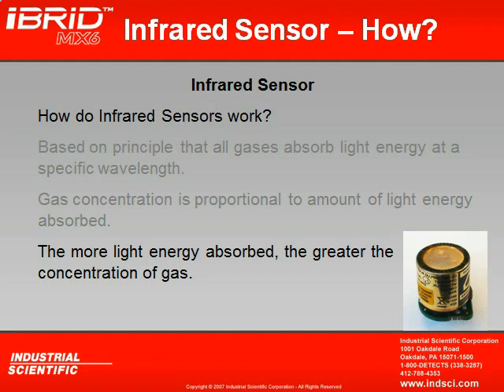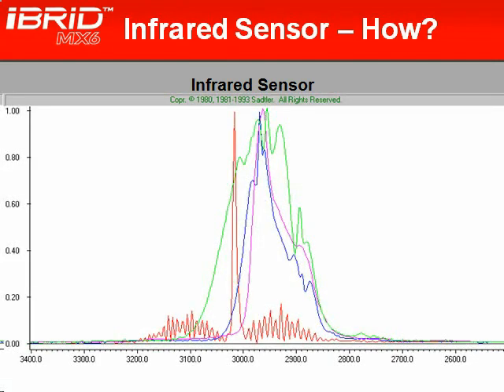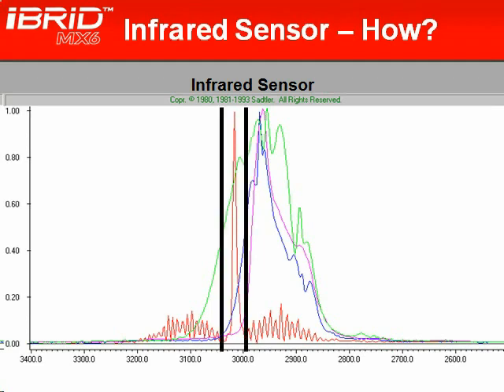So as we're trying to detect methane, we have to look out on the infrared spectrum to see where methane peaks. You'll see there in red, that peak right there at a little over 3 micrometers is actually methane, and that's where the greatest absorption of methane is going to occur. So we have to tune the optical sensor inside the infrared sensor to look at that 3 micrometers of light. The more of that light energy the infrared sees, the less methane gas. Why? The methane will absorb that light energy at a little over 3 micrometers, but the more of that light energy it sees, the less methane in the environment.